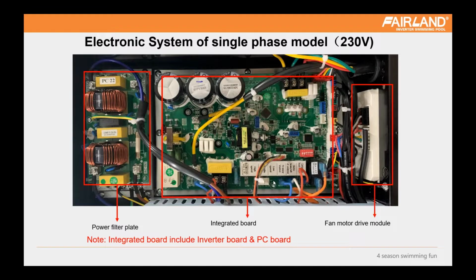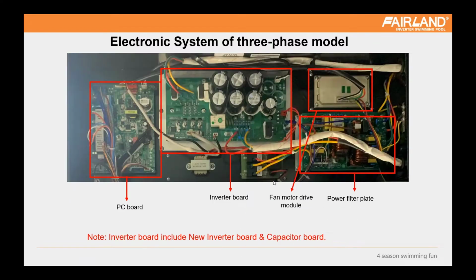Electrical system failure. This is the single phase model electronic system. This is the power filter plate, which protects against interference, and this is the integrated board, which drives the compressor running, collects all the data and gives orders to run the unit. And the third part is the fan motor drive module, which drives the DC fan motor.